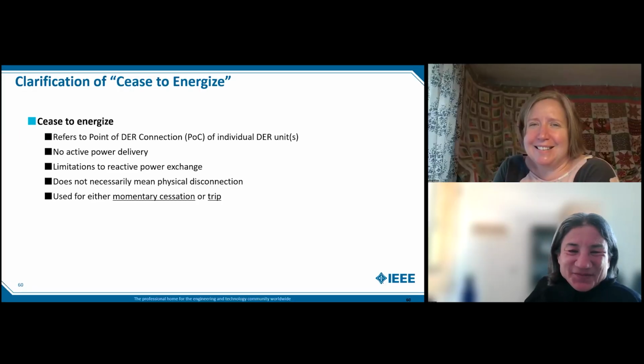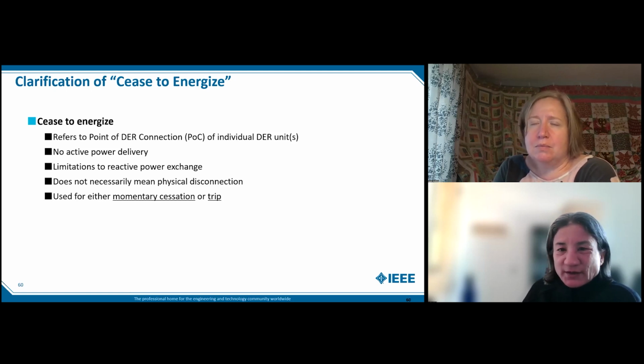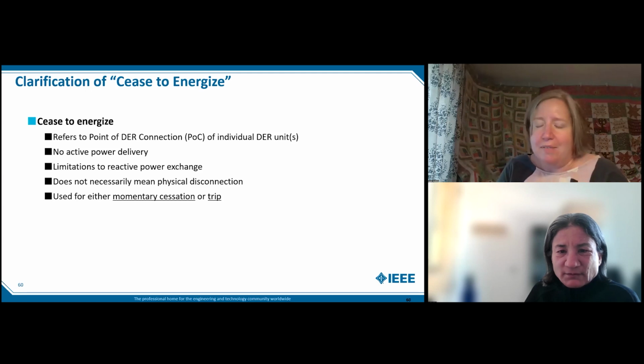I was wondering that. Okay, so in this case, this feeder was pretty easy. It was an ampacity limit, but you talked about interconnection studies. This is maybe a little outside the scope of 1547, but I think people would be really interested. Can you talk about what kind of studies you do at the feeder level? Do you get down into EMT studies, or is it case by case? We're not really there at PGE. Our planning engineers do a CYME study of the feeder. We haven't gotten much into EMT yet. I admit I'm a protection engineer, so I'm looking at loading and what I have at the substation and making some recommendations out the feeder for protection. But we tend to use CYME.